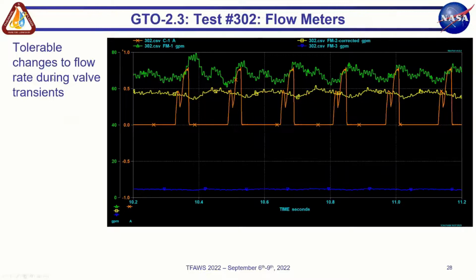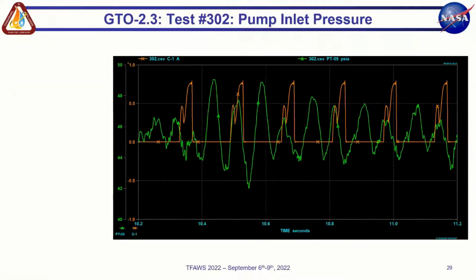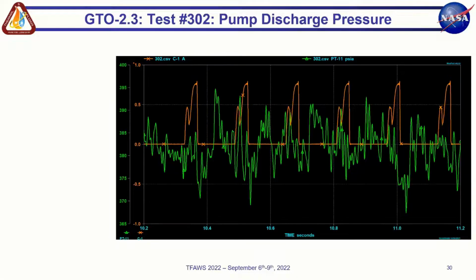This is a comparison of the flow meters. How much does the flow change during these valve transients? We're seeing that it ends up being a pretty tolerable flow change. It wasn't anything that was threatening the pump or the stability of our system. This is also a graph of the pump inlet pressure, and we see that these spikes are very small, as the mass of the liquid in the tank is attenuating things even further. And in the discharge pressure, it's harder to see the correlation here, but we're still showing the stability of the system, so that even when the thrusters are firing, the pump is not working against too much chaos.